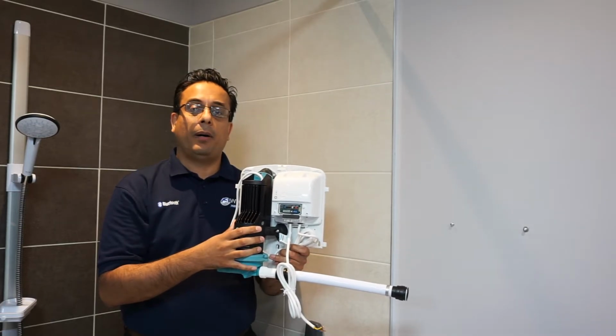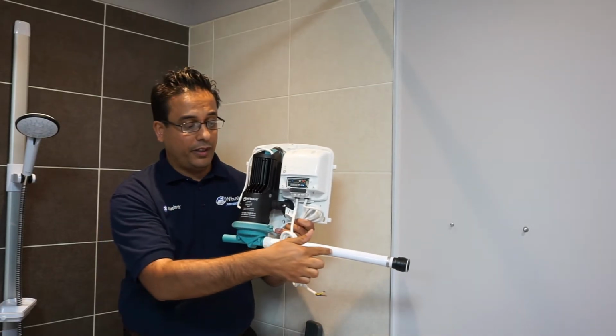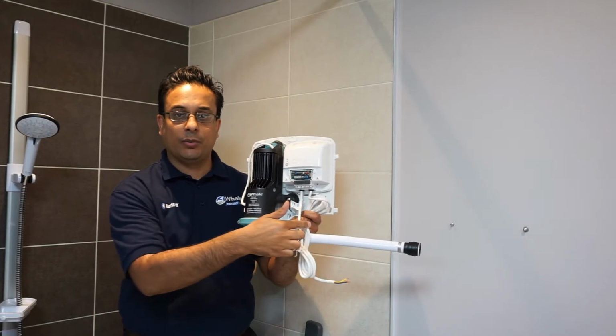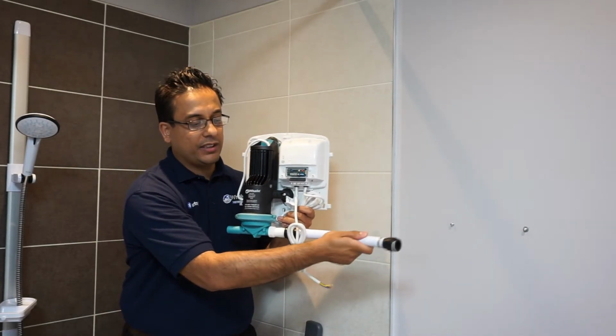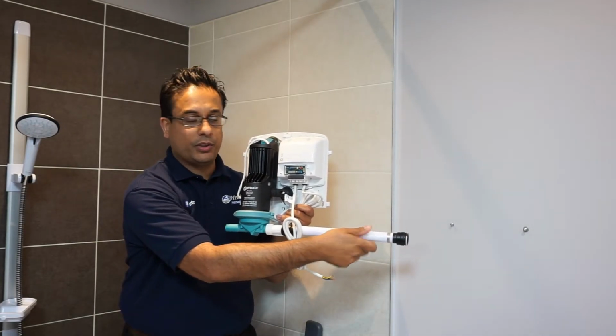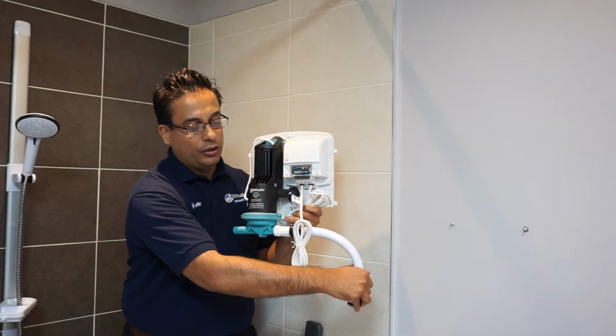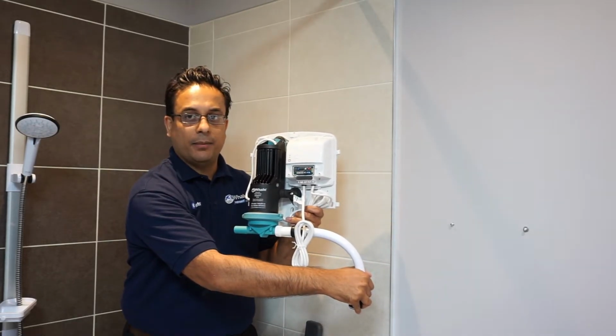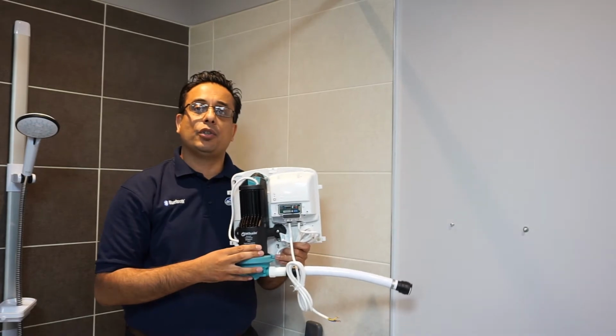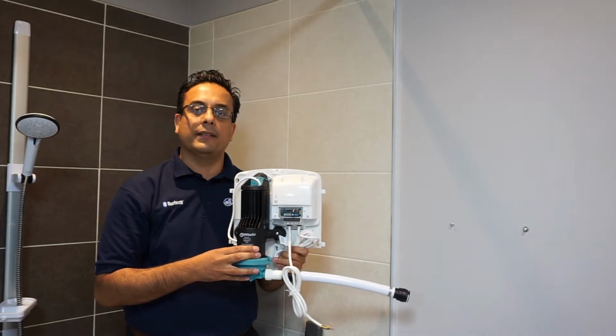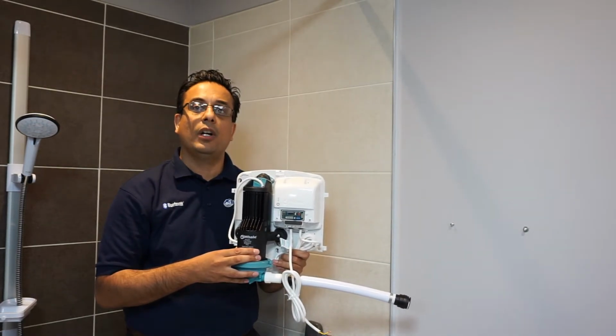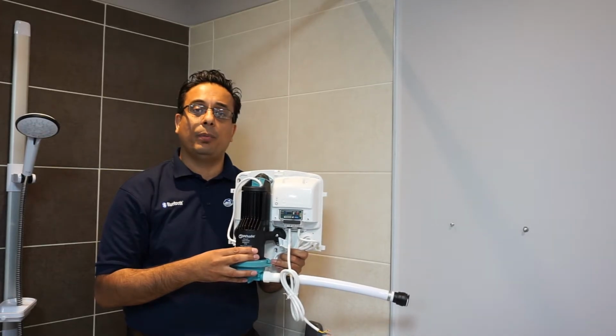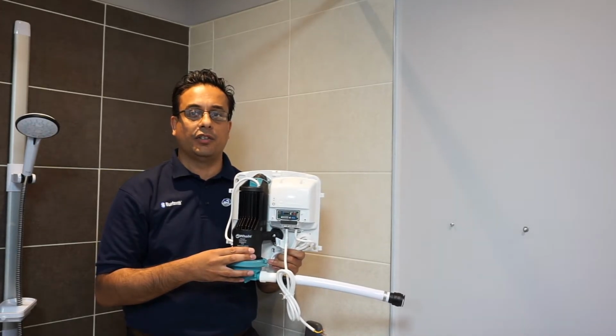When installing the pump, please use the Flexi Hoses provided on both the inlet and outlet. The Flexi Hoses can be used in a horizontal position and also used to form a radius bend. Please ensure that you only use formed bends under the floor and above the floor. 90-degree bends are not permitted in any part of the installation.